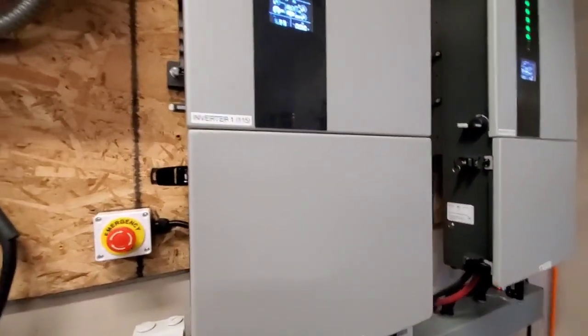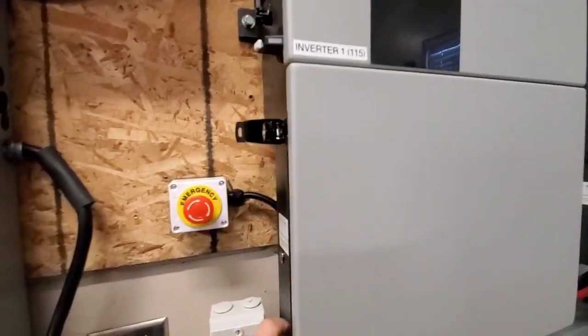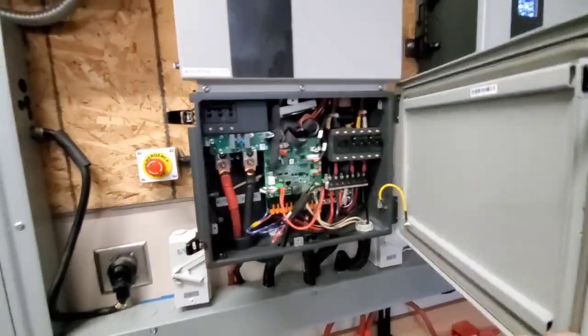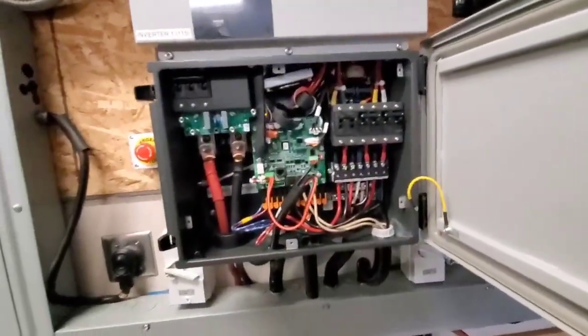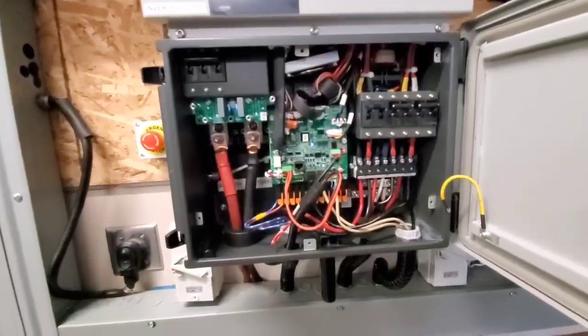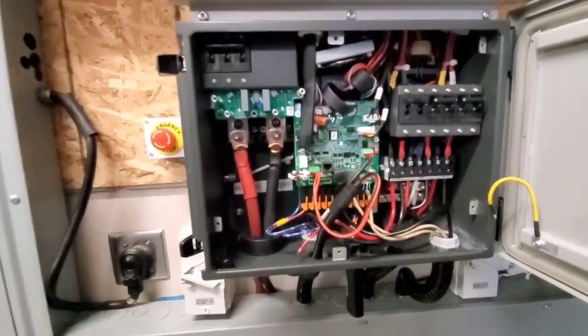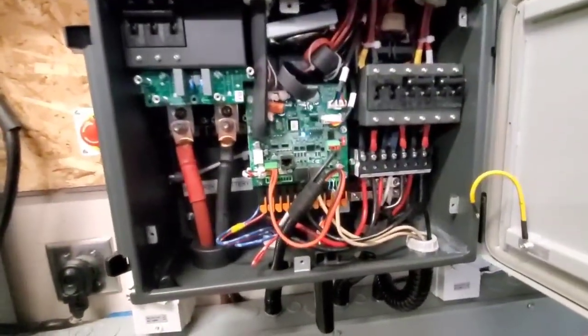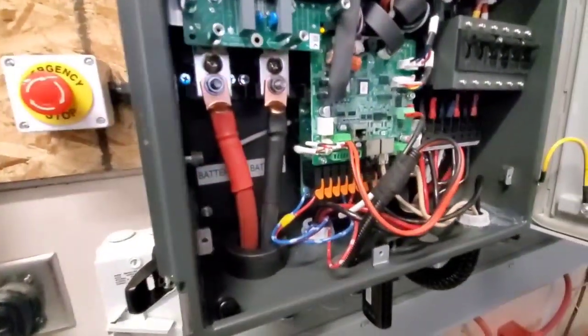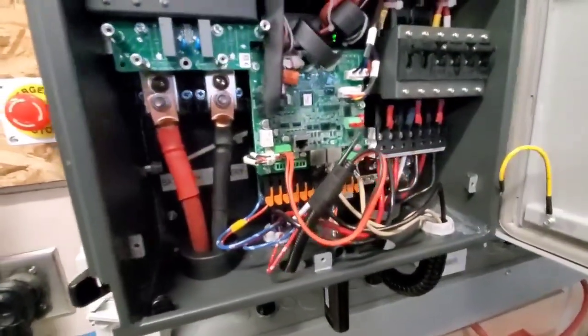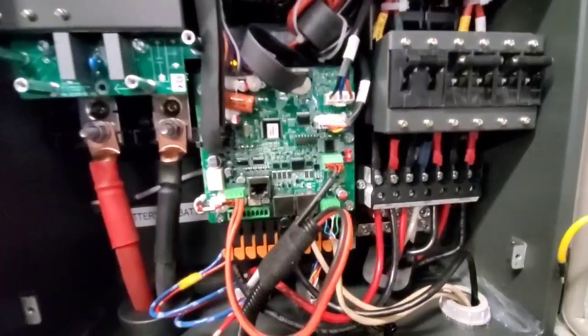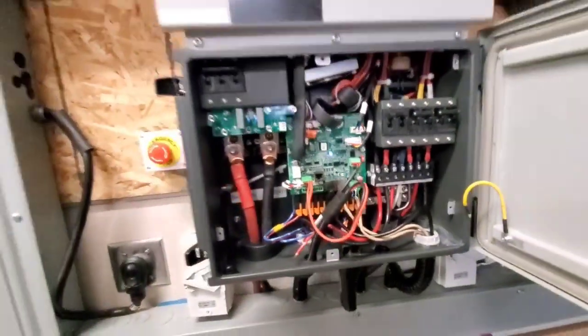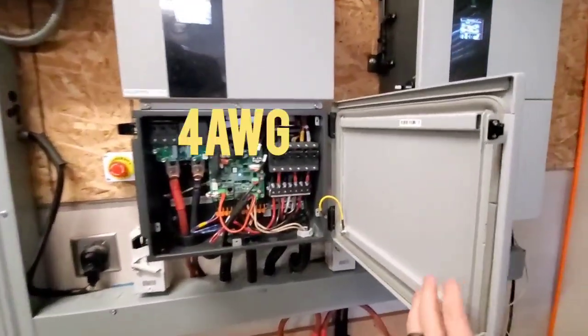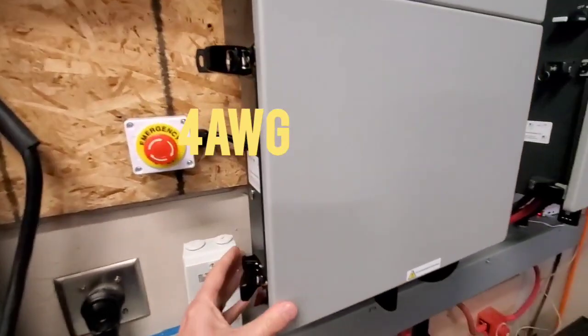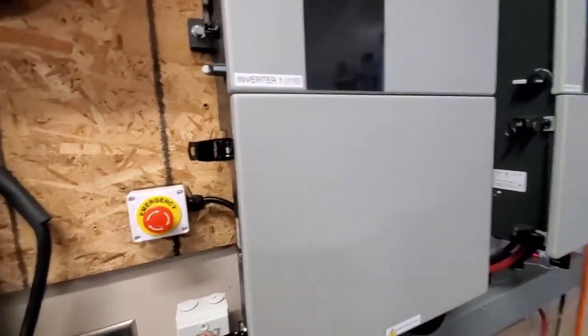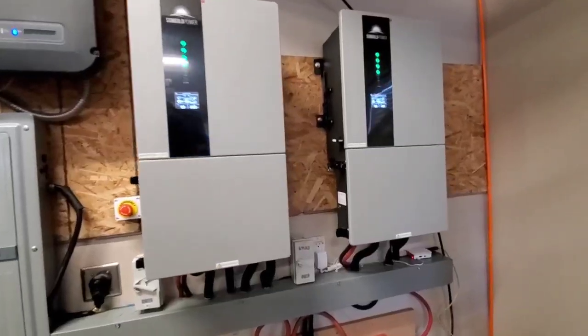Let's go inside. This is the main one, so it's got the CT clamps going into here, the battery cables go to each one, the BMS is in here, and the communication to both sides of the inverter. I did use 4-aught wire, which was really a lot of fun to run through everything.